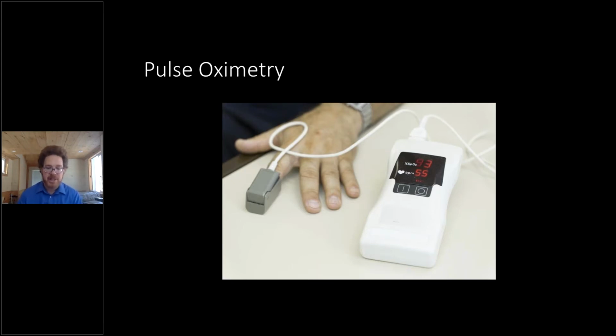The modern oximeter adjusts for the ebb and the flow of blood caused by your pulse and measures the oxygen level by calculating this ratio of red to infrared transmission several times a second. But the light has to pass through your skin for this measurement to occur. And in modern fingertip oximeters, it also passes through your fingernail, so nail polish could also disrupt an accurate reading. But the problem with pulse oximetry today is that these instruments tend to overstate the oxygen levels in people with more pigmented skin. But this is a problem that particularly shows up at lower oxygen levels, not at the highest end of oxygen levels where healthy people are.